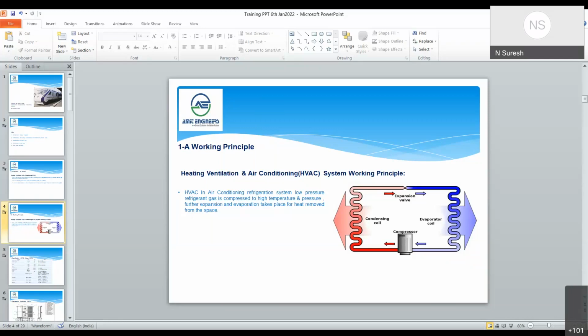That is how the condenser process happens, and then it passes through the expansion device where sudden expansion throttling happens. Due to that, the temperature drop occurs as desired to maintain the room temperature. There is an evaporator blower fan. In the evaporator, the room air and the fresh air are passed on one side of the evaporator and supplied through the duct. The blower keeps recirculating the air, and by the microprocessor controller, till the set temperature is reached, the compressor and condenser fans will be working.